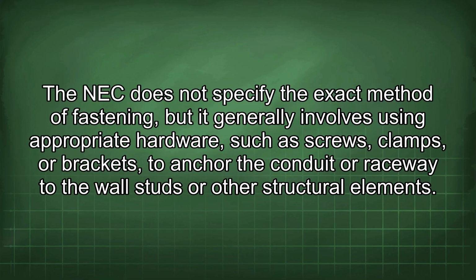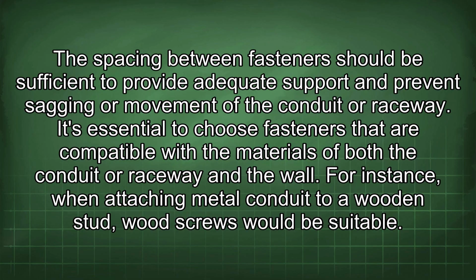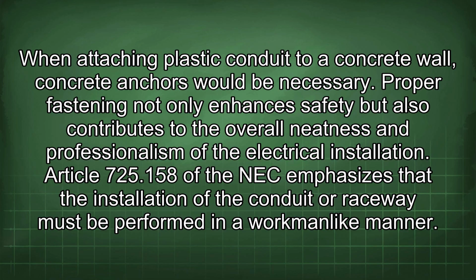The NEC does not specify the exact method of fastening, but it generally involves using appropriate hardware, such as screws, clamps, or brackets to anchor the conduit or raceway to the wall studs or other structural elements. The spacing between fasteners should be sufficient to provide adequate support and prevent sagging or movement of the conduit or raceway. It's essential to choose fasteners that are compatible with the materials of both the conduit or raceway and the wall. For instance, when attaching metal conduit to a wooden stud, wood screws would be suitable. When attaching plastic conduit to a concrete wall, concrete anchors would be necessary. Proper fastening not only enhances safety but also contributes to the overall neatness and professionalism of the electrical installation.